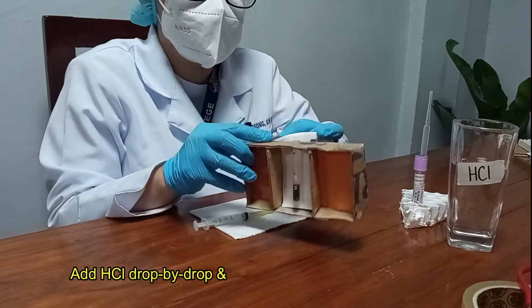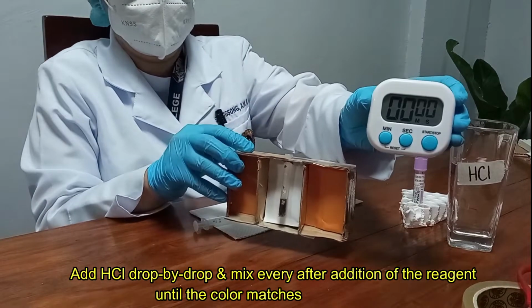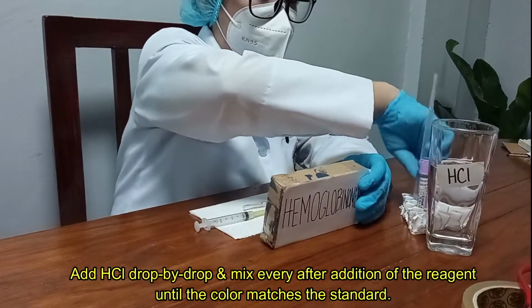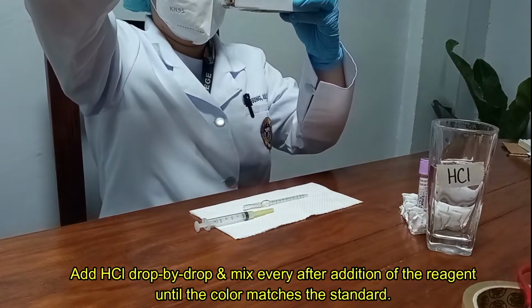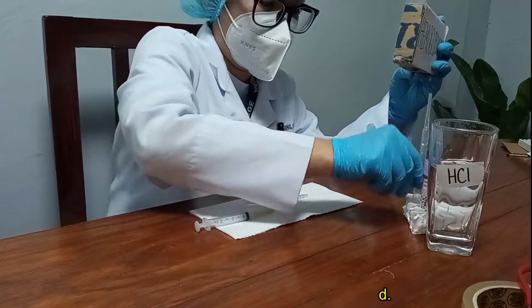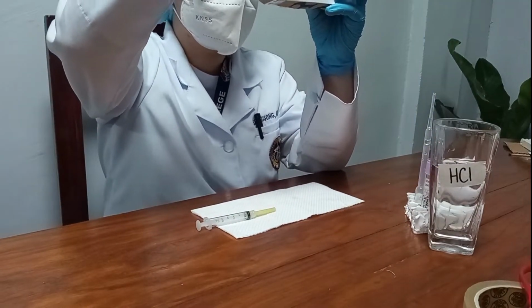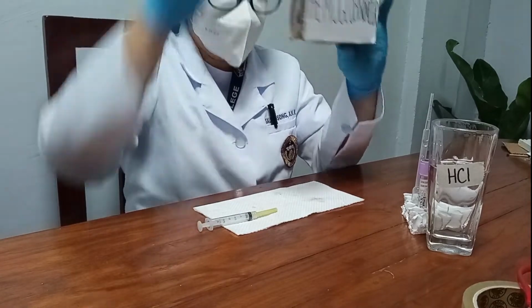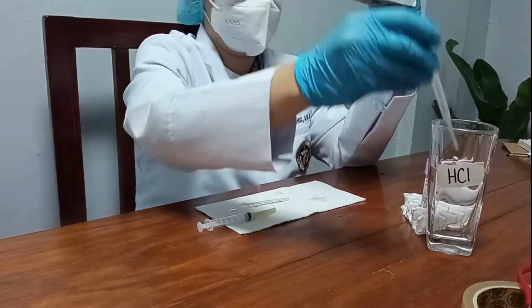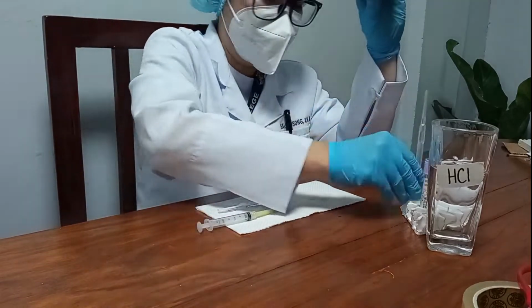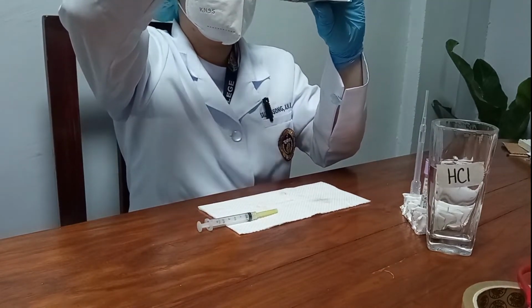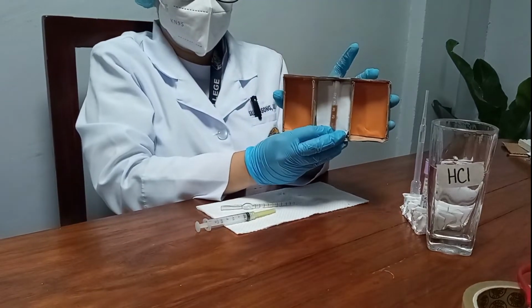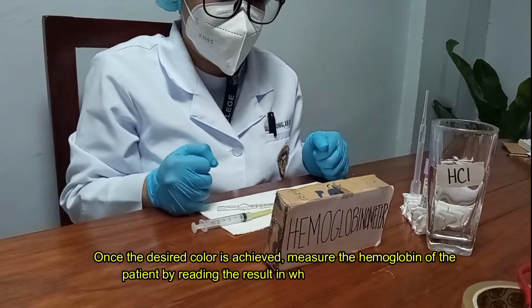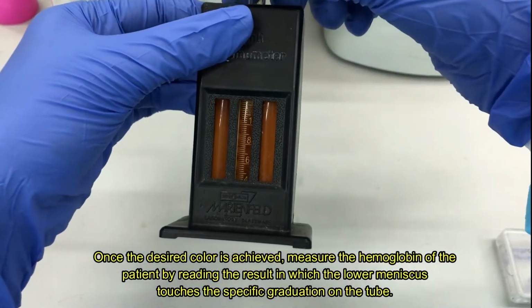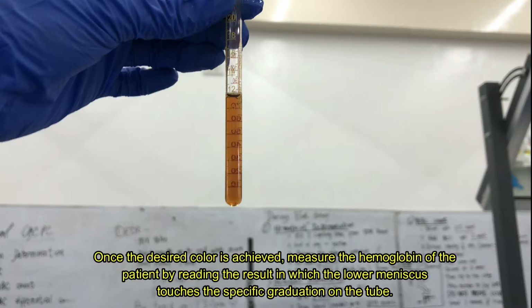Afterwards, add hydrochloric acid drop by drop and mix after every addition of the reagent until the color matches the standard or the color in the hemoglobinometer. Once the desired color is achieved, measure the hemoglobin of the patient by reading the result in which the lower meniscus touches the specific graduation on the tube.